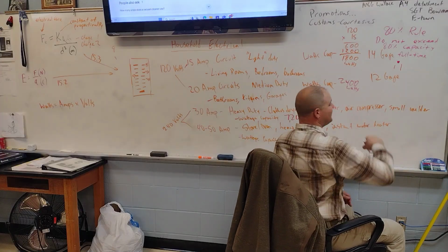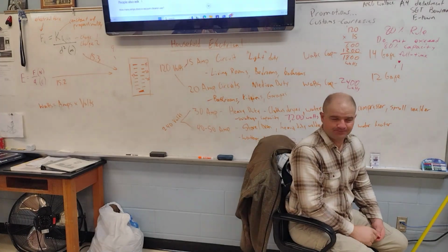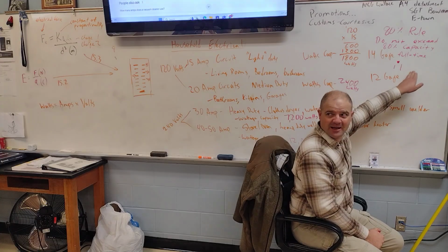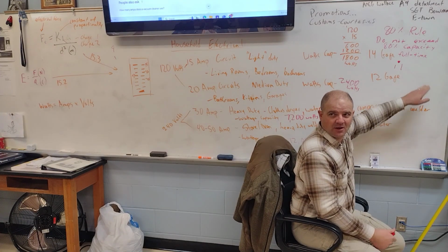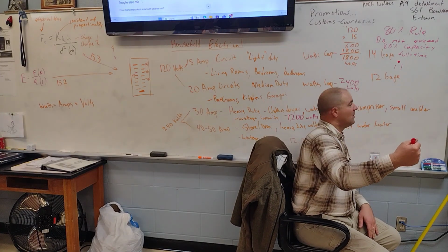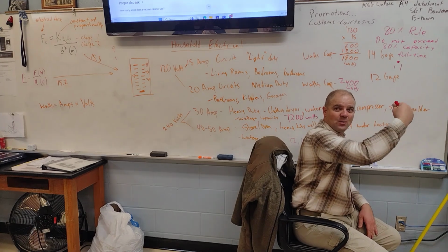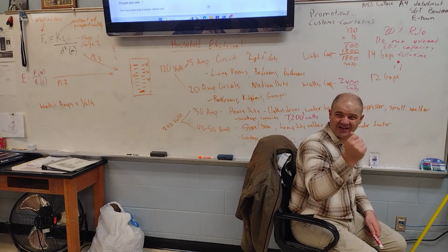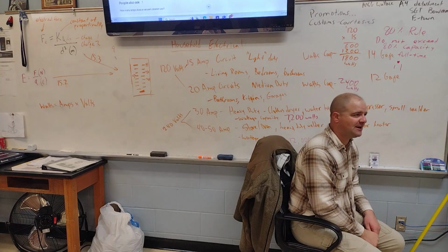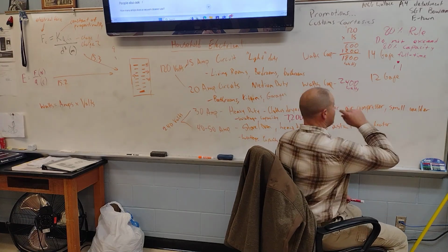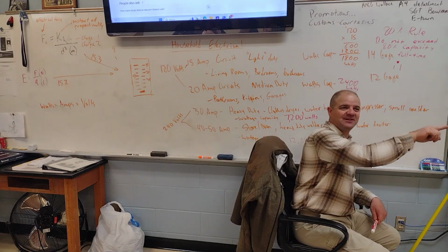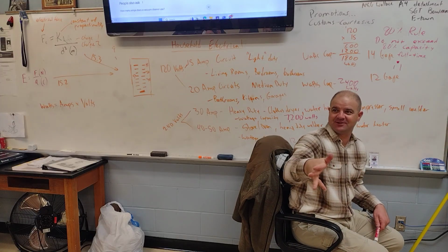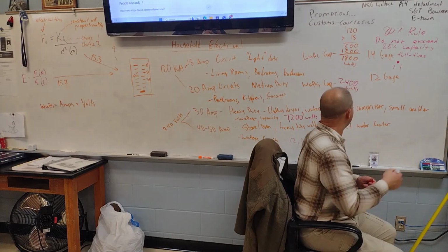But that is a 15 amp outlet. Plugs will plug in there and, because of the style of plug, they won't be able to draw more than 15. But if you have multiple things plugged in along the circuit, could you exceed 15 still? Yes, you could. So you still have to be careful.